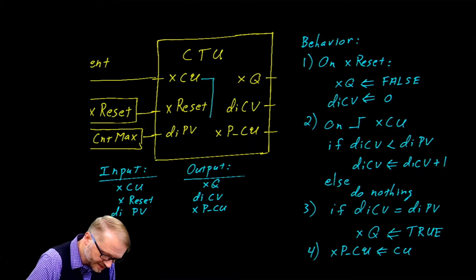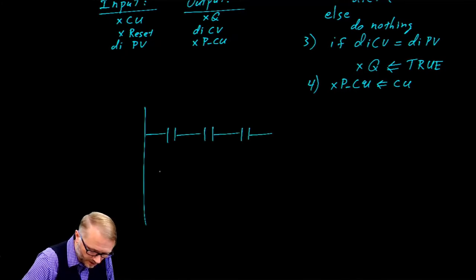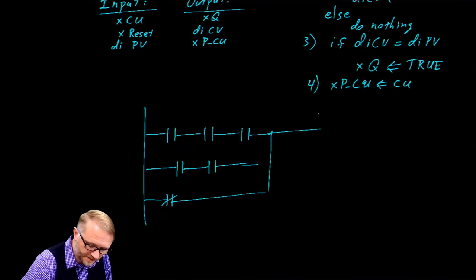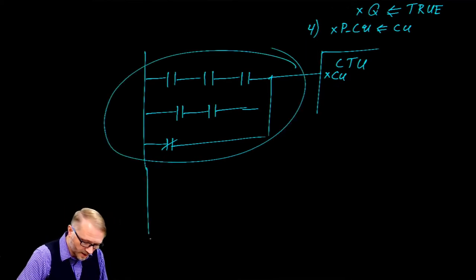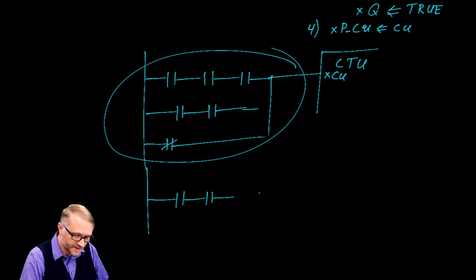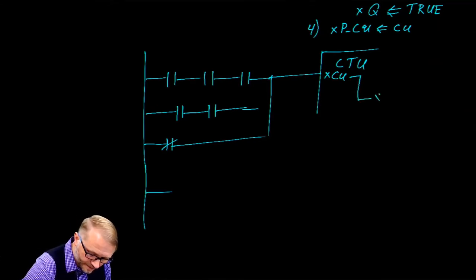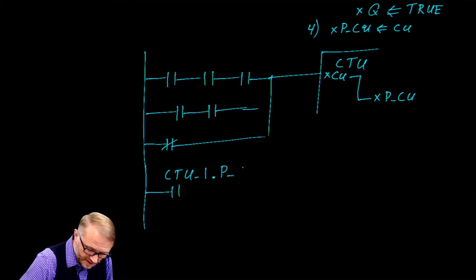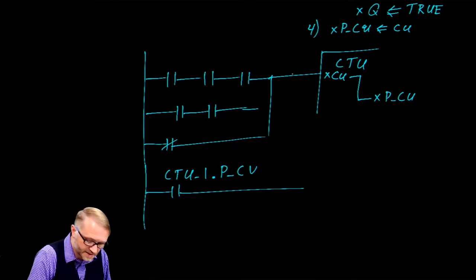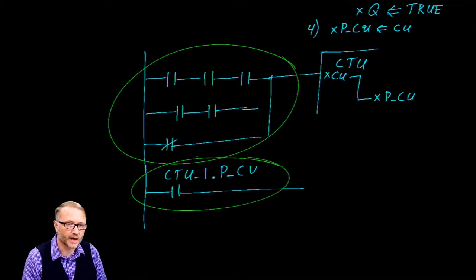We mentioned this already when we said that these were effectively wired together. Suppose you had a complex rung that fed into a counter. Suppose you needed to reuse this code on the next rung. Rather than repeating all of the code, you could instead simply say we want a contact from counter one dot previous current value. And what that does is it takes all of this and replicates it right there. Again, it can make your code a little more compact and easier to read.